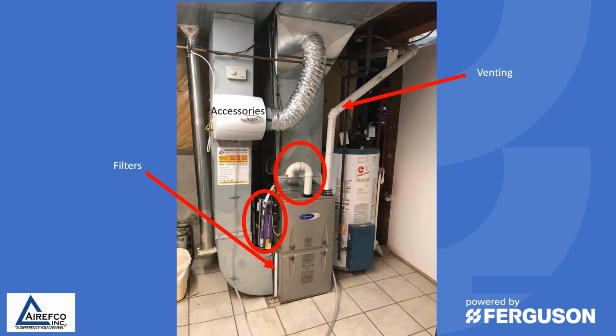Another thing we observe is that the combustion air for the furnace is being drawn from the space. Now, normally this is okay and is approved by the manufacturer, but you need to take into consideration a couple of things. Number one, the environment that the furnace is living in. Usually furnaces are in a laundry room or in a workshop where there are caustic materials that are being used, or dish soap, or things that could damage the secondary heat exchanger. So if you're pulling the air from inside the home or inside the space, you want to make sure there's enough air and that it is good air that we're putting into the furnace.